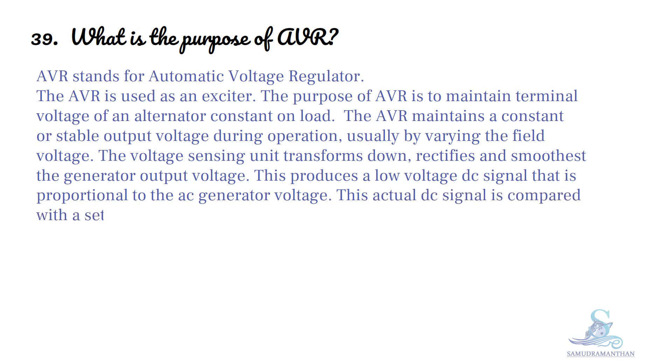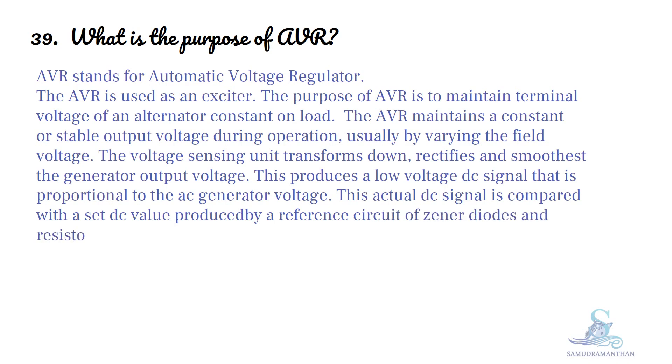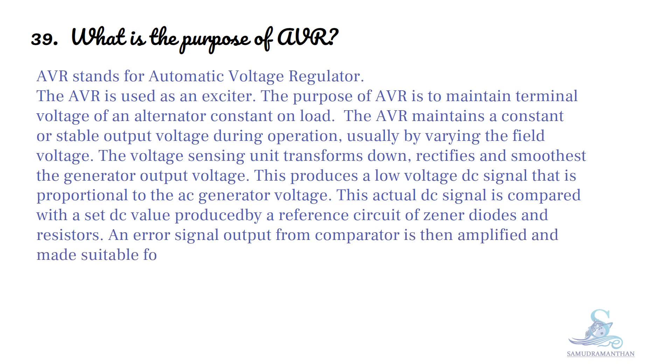This actual DC signal is compared with a set DC value produced by a reference circuit of Zener diodes and resistors. An error signal output from the comparator is then amplified and made suitable for driving the field circuit regulating thyristors.